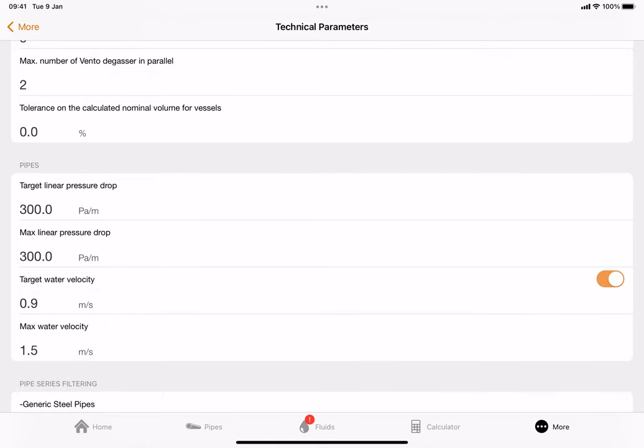The CIBSE guides state that target linear pressure drops are between 300 and 500 pascals per meter - so for every one meter of pipe work, up to 300 pascals of resistance. I try to stick to this to make the choices of your pipe work and fittings as close to what the CIBSE guide argues for. I would always say stick to 300, so get your target linear pressure drop to 300 pascals per meter and your maximum linear pressure drop to 300 pascals per meter.